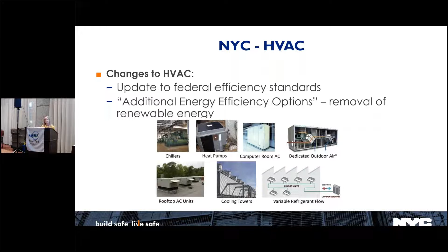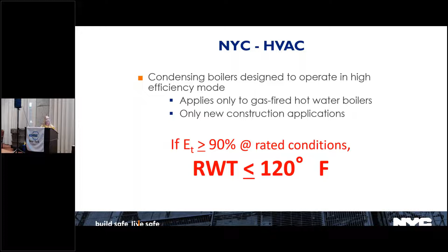Also, this came from our advisory committee. My team was seeing a lot in plan examination that condensing boilers being designed into buildings were not operating in condensing mode. So that was a change made in the code. It doesn't mandate that you have a condensing boiler, and this probably goes away with the new electrification law, but for gas-fired boilers, if the designer chooses a condensing boiler, it must be designed to operate in condensing mode.